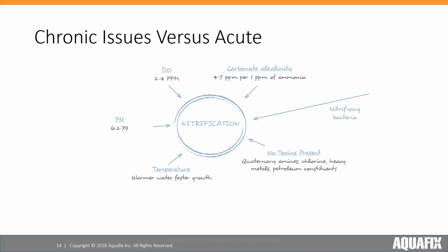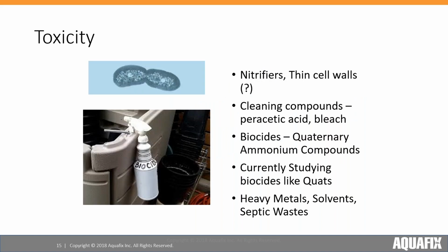So this first slide here, we're going to look at what's commonly the most common of the acute issues where the nitrifying bacteria are simply lost for some reason. One major reason that they can be lost is high flow rates.